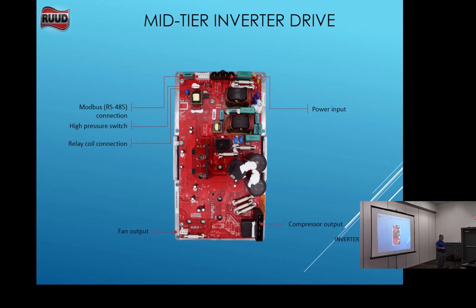You got power coming in up here. You got power coming out here. Board's good. Power coming in, no power coming out. Board's bad. It's really rough. I will tell you, if you see right here next to these fuses, they've had a couple in the field that we've heard about where they were getting an inverter fault. Okay, the system would not run.